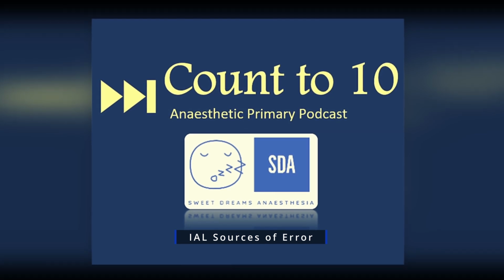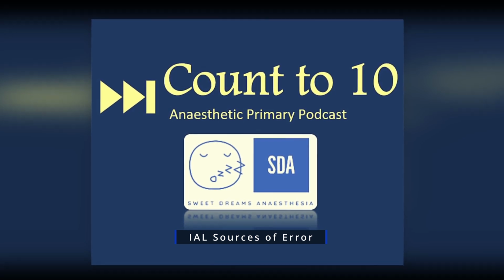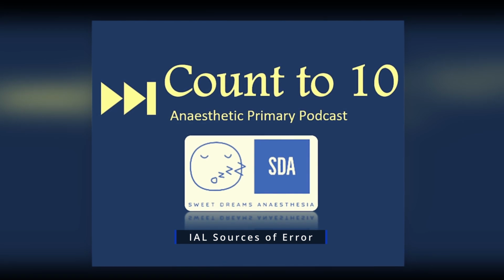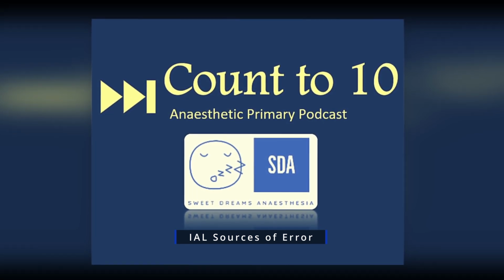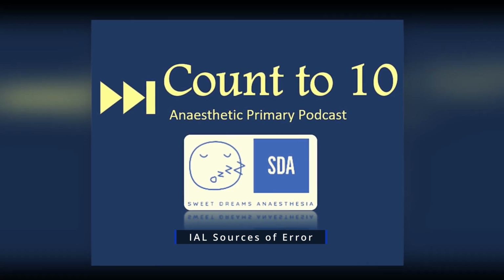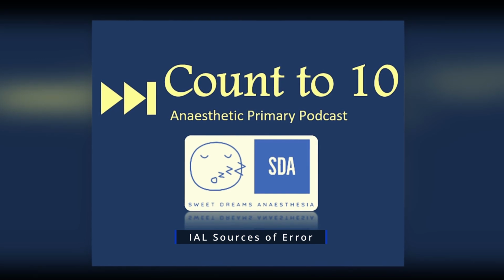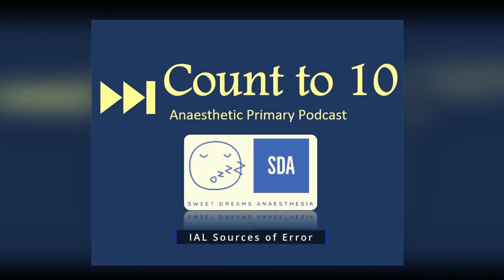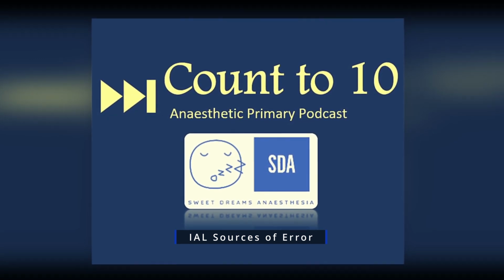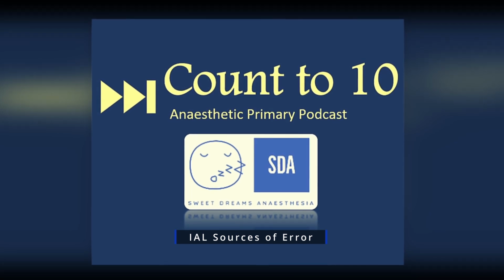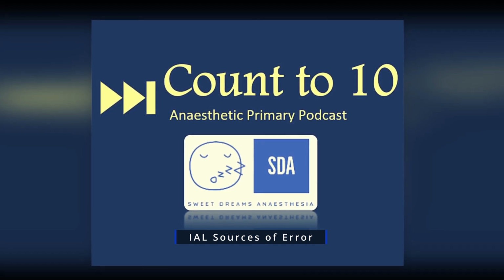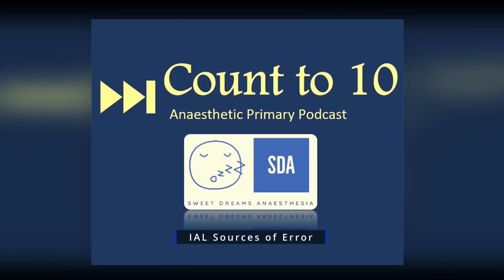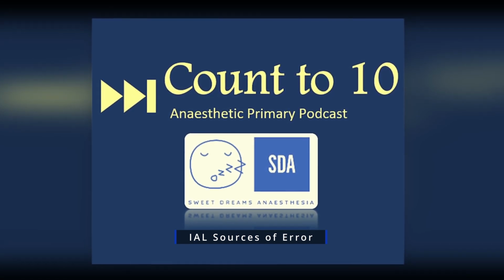So what we end up doing when talking about damping is referring to this thing called the damping coefficient, and more specifically a term called optimal damping. In an arterial line, the optimal damping occurs at a damping coefficient of 0.64. This is because if there's too much damping, the system loses too much of its energy before it gets to the transducer. If there's too little damping, there's too much oscillation occurring, and that oscillation will continue even when a new arterial pulsation has arrived.